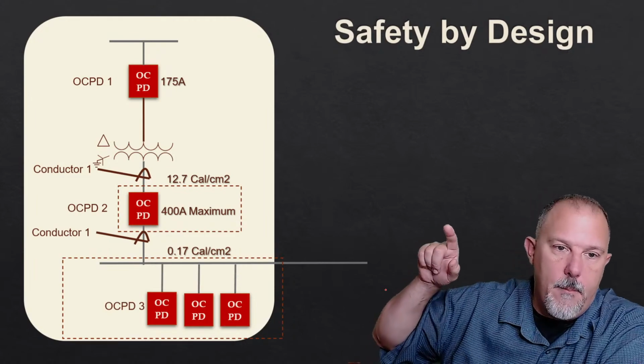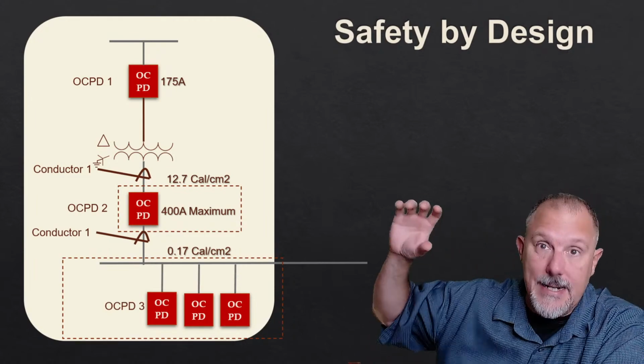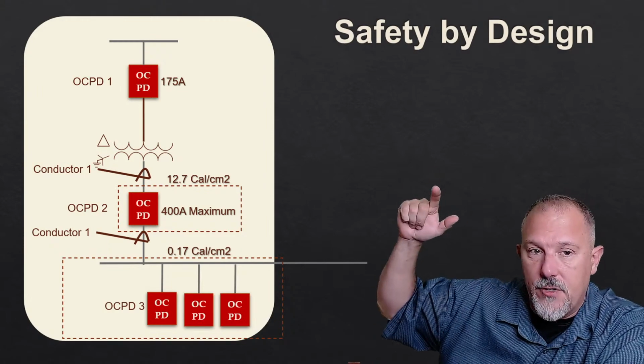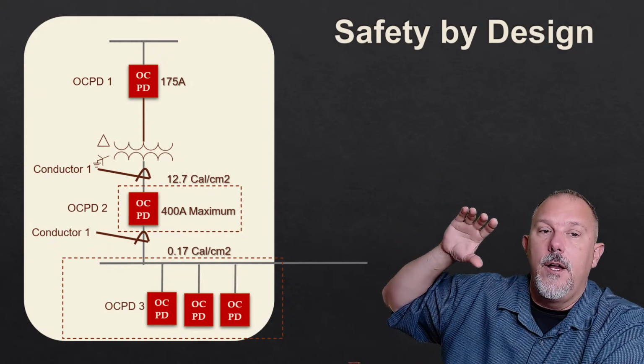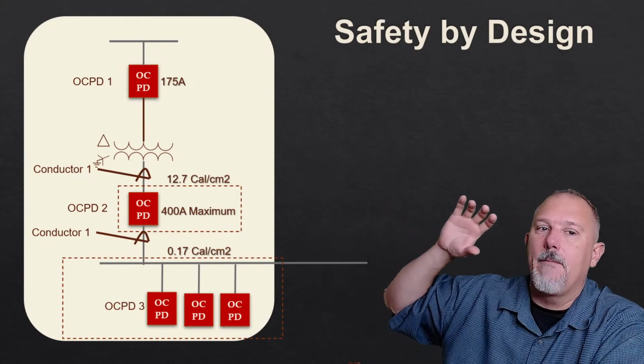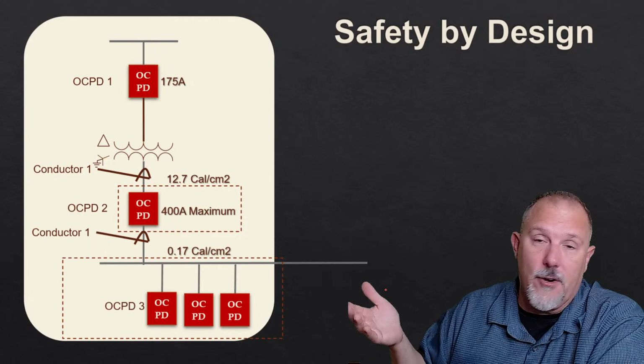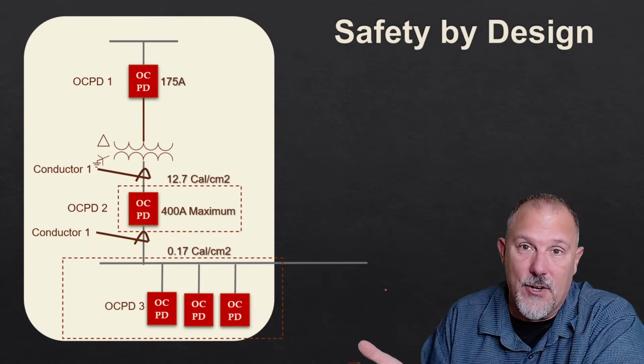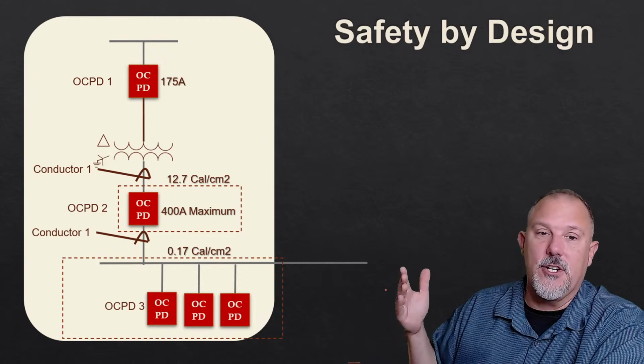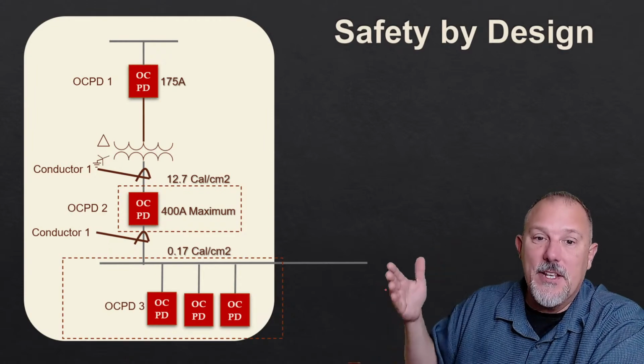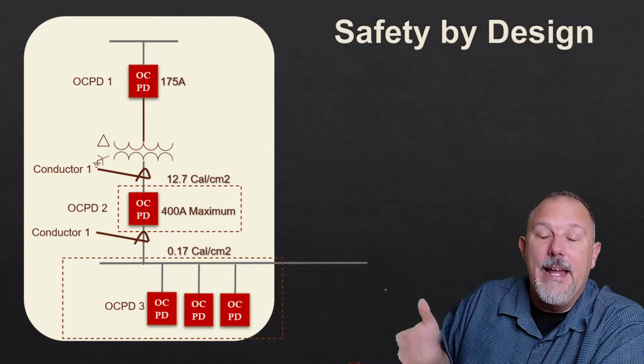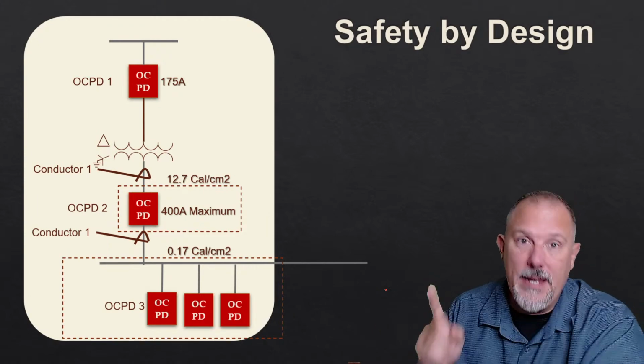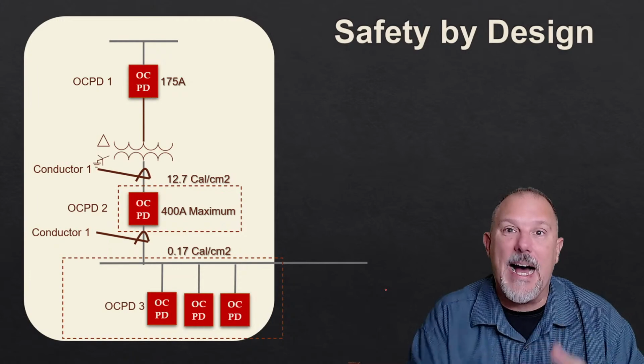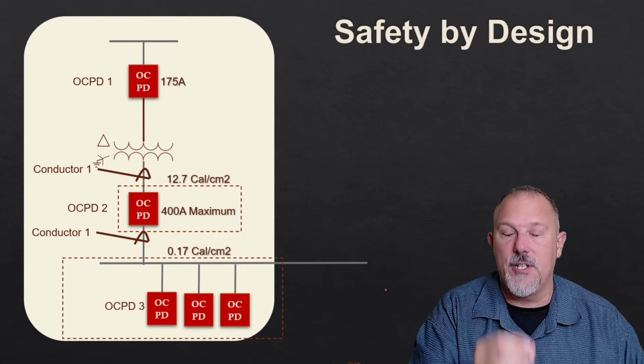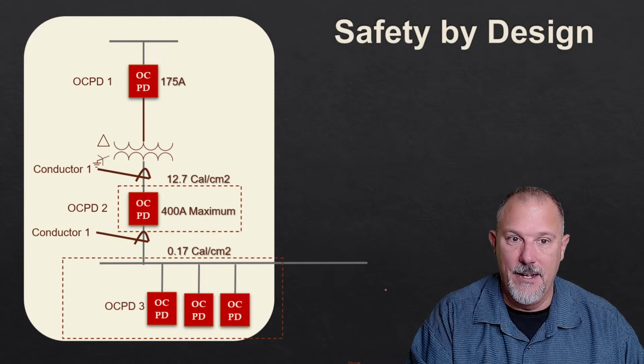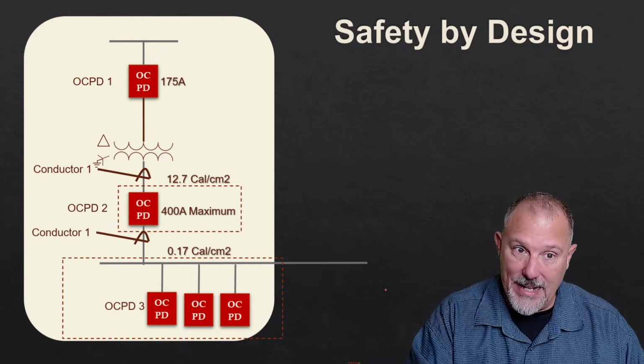And if I have my main overcurrent device, my protecting overcurrent device on the secondary of that transformer, in a separate enclosure, if it's 1600 amps, I know it's going to have an arc reduction maintenance switch on it. It has to have arc reduction technology. So my arcing current and my incident energy is going to be low at this first piece of equipment. And think about this. Where is that going to be? It's going to be probably right next to this equipment. I can very easily establish an electrically safe work condition. That's the value of this.